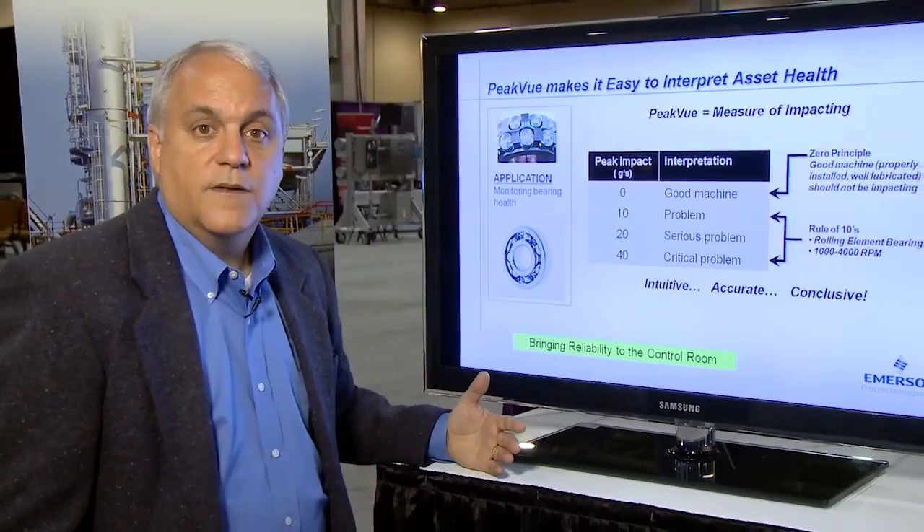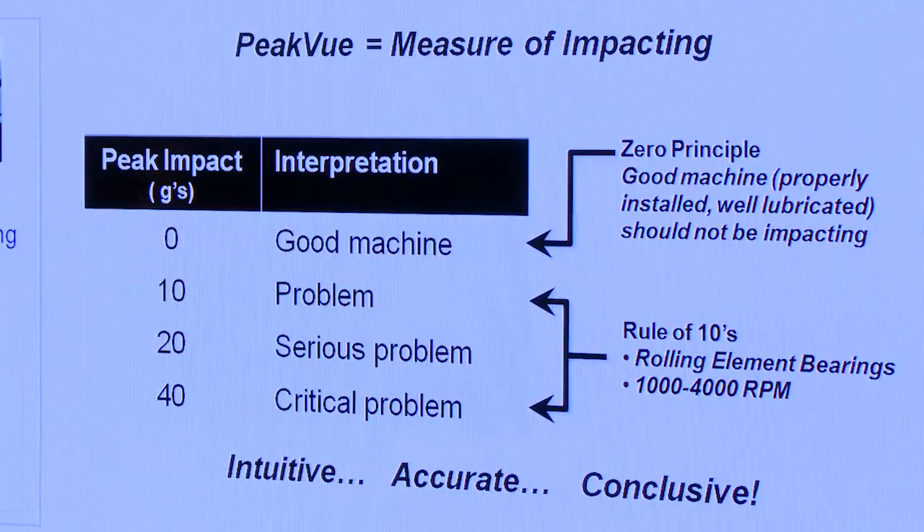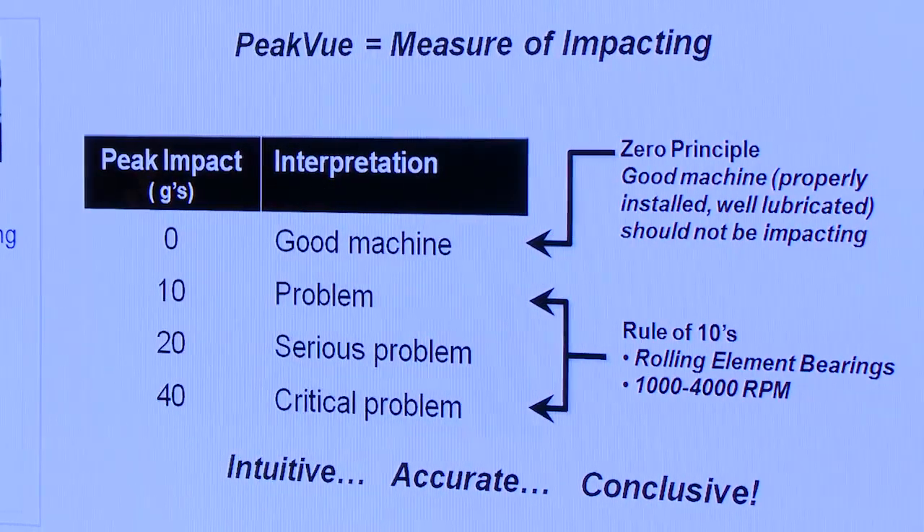The first principle used to monitor PeakVue is referred to as the zero principle. The zero principle states that a good machine, properly installed and well lubricated, should have impacting that is at or close to zero. Very intuitive — zero is good.